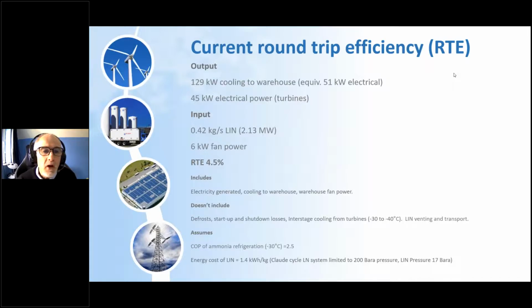We got 129 kilowatts of cooling to the warehouse. Now we have to look at the value of that actual cooling. Taking the COP of the ammonia refrigeration system as 2.5, that would be the equivalent of 51 kilowatts of electrical input to create that cooling to the cold store warehouse, which was running at about -20 degrees C.